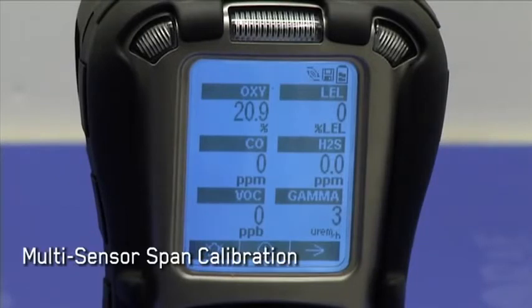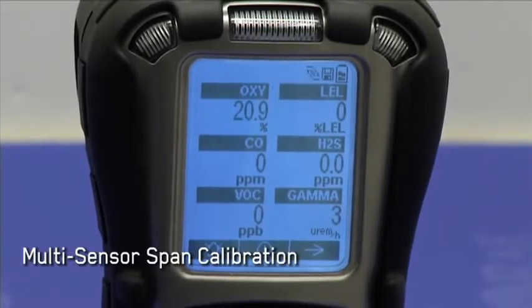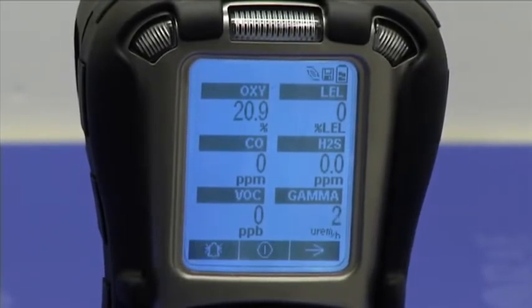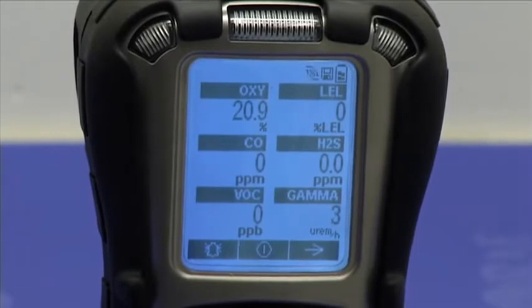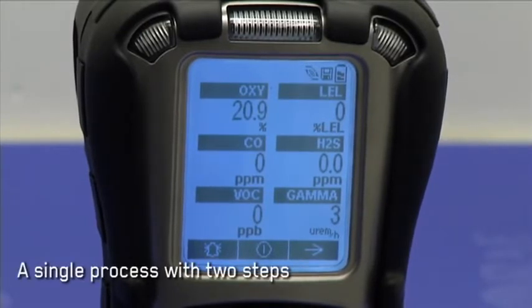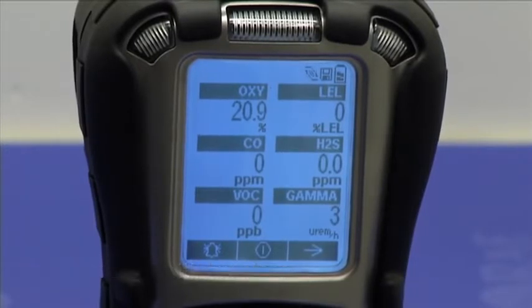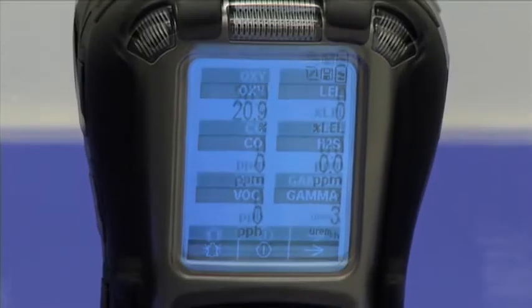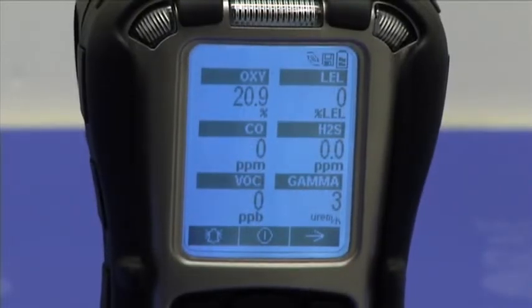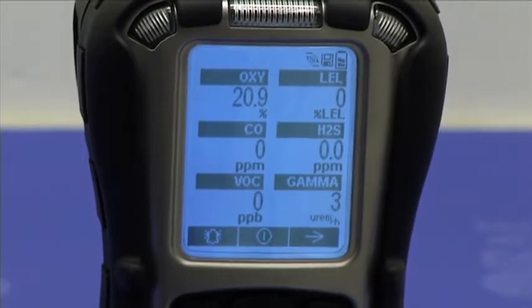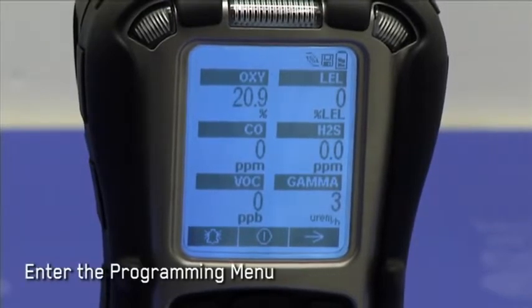The multi-sensor calibration process for this particular MultiRAE Pro would involve 2 steps, and the instrument is going to intelligently guide me through these 2 steps. The first step will involve a simultaneous calibration of the oxygen, LEL, CO, and H2S sensors using the 4-gas mix, followed by the calibration of the PID sensor. To perform any calibration-related routine, I first need to enter the programming menu.